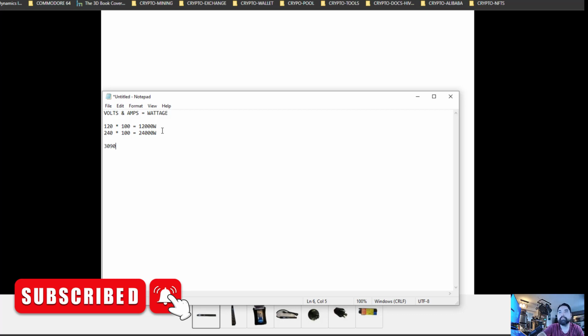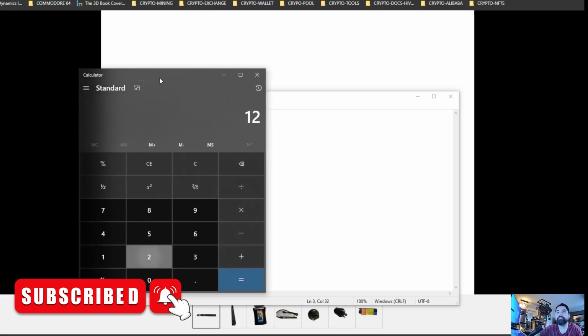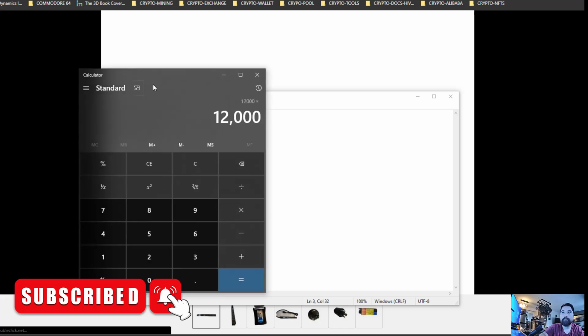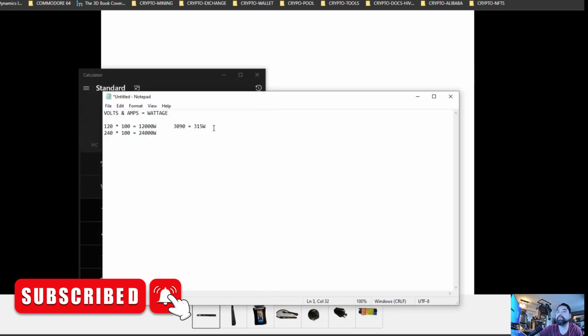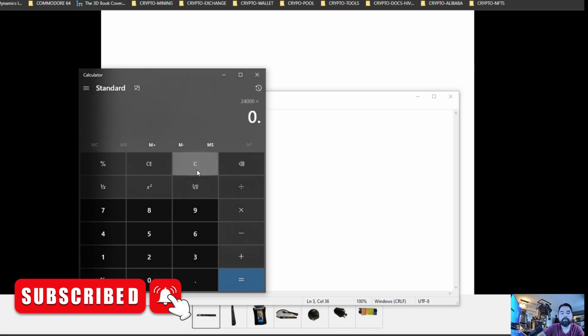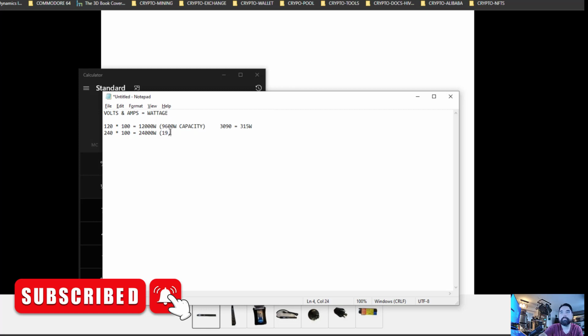Now, we measure GPU rigs and GPUs in terms of wattage. For example, a 3090 might use around 310 to 315 watts. So if you filled a rig with 3090s, you'd get a maximum capacity of 12,000 watts at 120 volts. Applying the 80% rule gives you 9,600 watts of usable capacity. For 24,000 watts at 240 volts, 80% gives you 19,200 watts capacity - almost twice the amount.